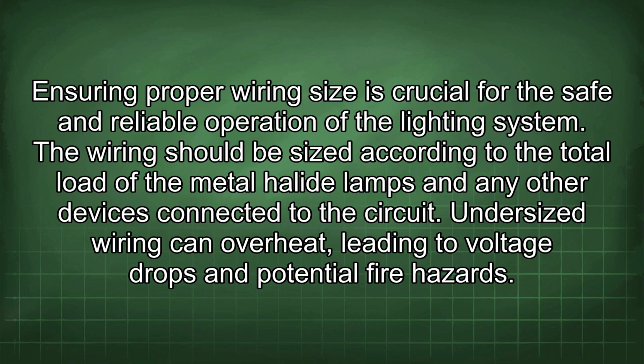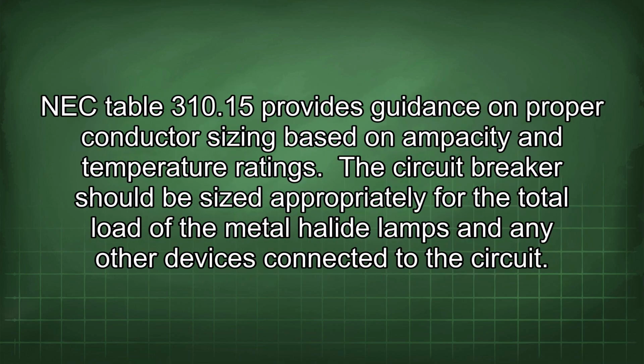Ensuring proper wiring size is crucial for the safe and reliable operation of the lighting system. The wiring should be sized according to the total load of the metal halide lamps and any other devices connected to the circuit. Undersized wiring can overheat, leading to voltage drops and potential fire hazards. NEC Table 310.15 provides guidance on proper conductor sizing based on ampacity and temperature ratings.